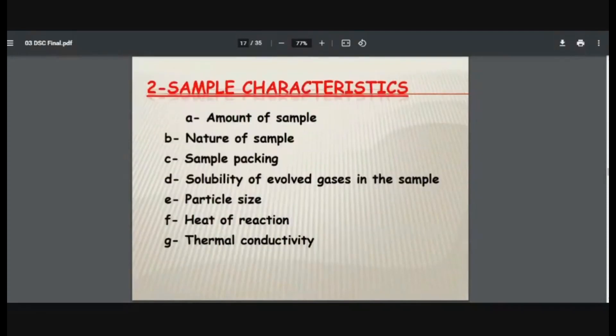Then there are sample characteristics: nature of the sample, whether it is solid, liquid, whether it is crystalline, whether it is amorphous. Then sample packing, whether it is compactly packed, loosely packed, what is its porosity. Then solubility of evolved gases in the sample. Now why is solubility important? Suppose it is a liquid and evolved gases are getting solubilized. So solubility many times is endothermic or exothermic process. So you are getting evolution of gas, one thing. So that is accompanied by solubilization. So two processes happening simultaneously. So you may observe unusual peaks. Particle size we have seen already. Heat of reaction, endothermic or exothermic, and thermal conductivity of the sample. If it is good conductor of heat, you will get uniform heating, you will get sharp peak. If it is not that good thermal conductor, then the peaks may not be sharp.